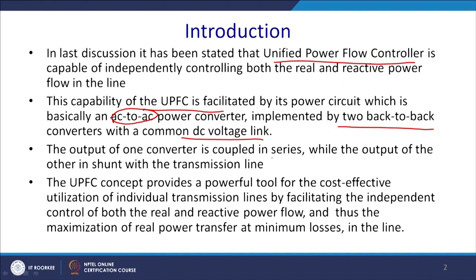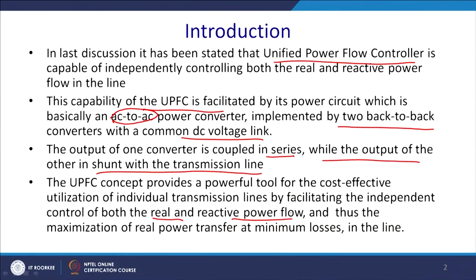The output of one converter is coupled in series, while the output of the other is connected in shunt with the transmission line. The UPFC concept provides a powerful tool for cost-effective utilization of individual transmission lines by facilitating independent control of both real and reactive power flow, thus optimizing real power transfer and minimizing losses.